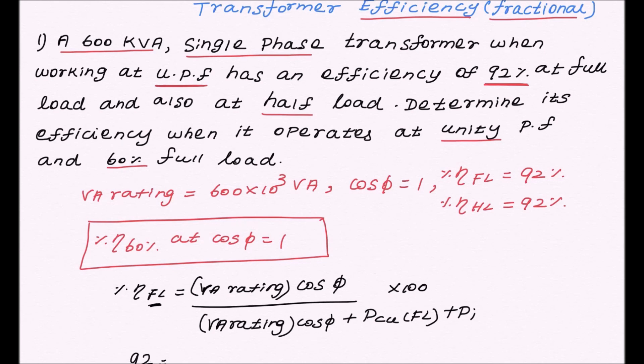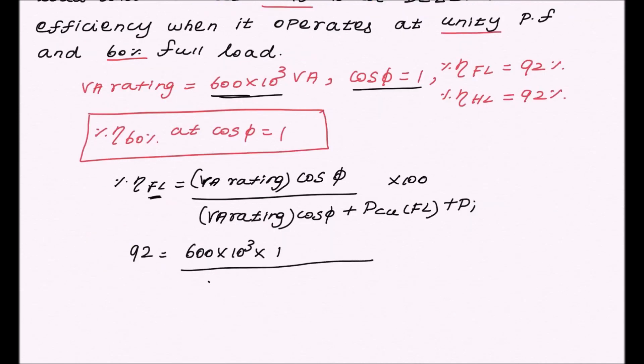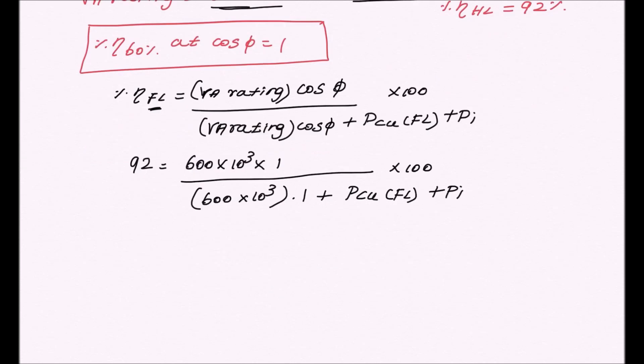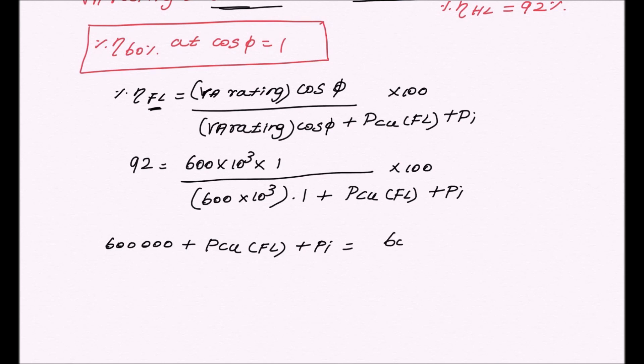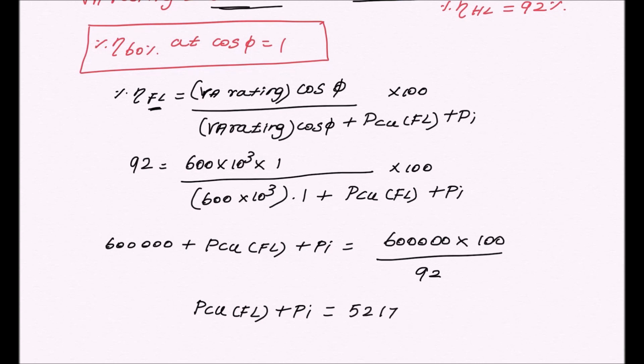Substituting: 92 = (600 × 10³ × 1) divided by (600 × 10³ × 1 + full load copper loss + iron loss) × 100. From this, 600 × 10³ + full load copper loss + iron loss = 600 × 10³ × 100 / 92. Solving this equation gives: full load copper loss + iron loss = 52,173.913. Mark this as equation number 1.